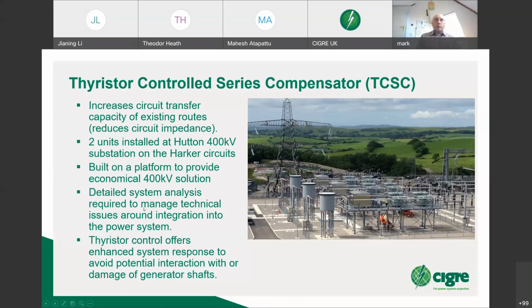And on our units, when we were doing the analysis, we identified that one of the key issues we now need to start catering for is the potential interaction with other assets. Generally, SVCs and STATCOMs, people tend to design in isolation, maybe needing to cater for harmonics. But as you start looking at series compensation, you now have to start thinking about everything around it, in particular generators in this case, and subsynchronous oscillations. What you don't want is, under certain conditions, a resonance between the capacitance of these devices and a nearby generation or other sources of active control.